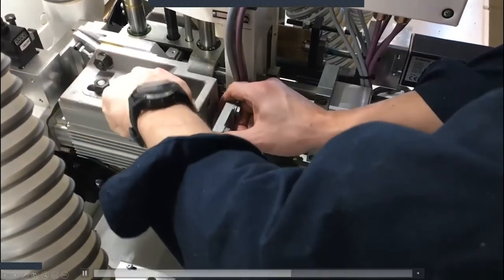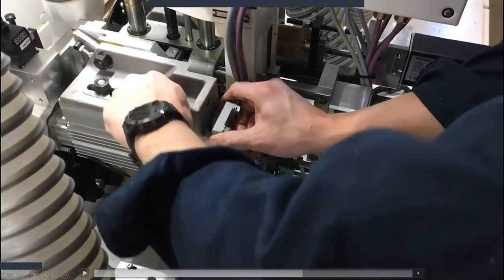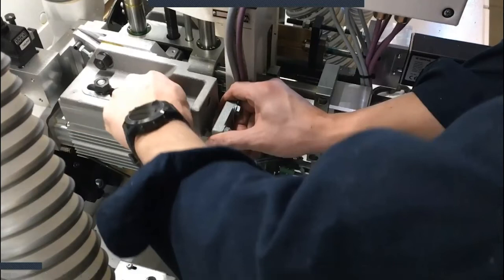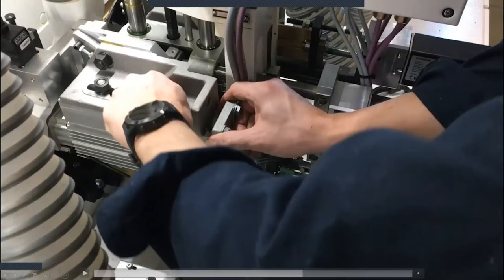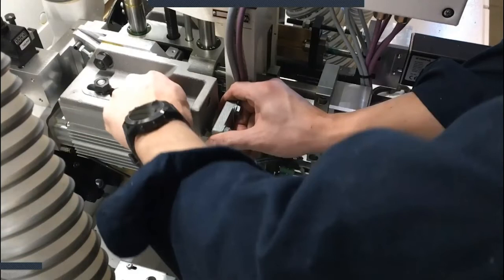So once I disconnect these quick disconnects, note that I had already loosened these nuts. I don't want anybody to think that they should be this loose - they should be tight, but not overly tight. This is an aluminum block underneath here, and those studs will pull out of that aluminum block, so please do not wrench those nuts down. They just need to be nice and snug.